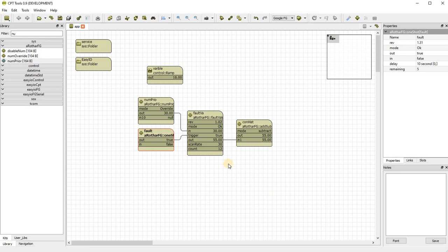So again, you can configure this to be a minute, which seems a bit redundant because if it's more than a minute, you can actually use the COV to capture the history as it changes. But if it's less than that, if you wanted to know what it was between 1 and 2 seconds ago, you could set this up to 1 second, and every second it will record the value.